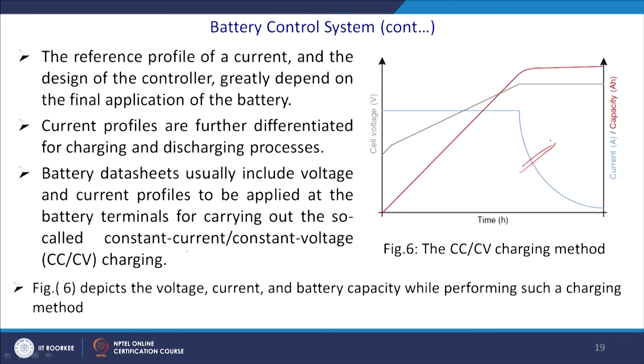So, there are different kinds of charging methodologies. In the constant current charging mode, a constant current is applied at the battery terminal and it is ensured by the current control loop of the DC to DC converter to which the battery is attached. The battery cell should be properly monitored so that overcharging and over discharging are avoided, that is, we need to ensure that, otherwise there will be a fast fall or fast rise in voltage. Once the cell voltage reaches the peak charge, the controller switches to the constant voltage mode.